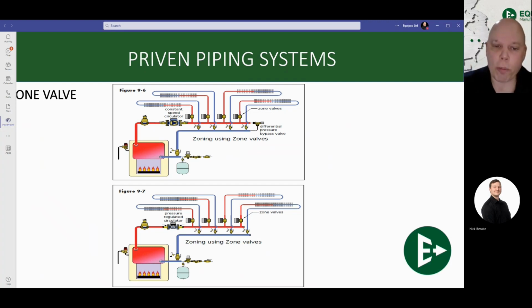That is, when all the valves are open, it sees very little pressure back against it. It knows that all of the zones are open. It's operating at full speed. As one zone closes and two zones close, it sees more and more resistance against its flow because it's pushing against closed zone valves. So it's going to slow down. It's going to create less flow to get through the other zones that are still remaining open. That's the difference between a fixed speed circ with a differential pressure bypass and a variable speed circulator.